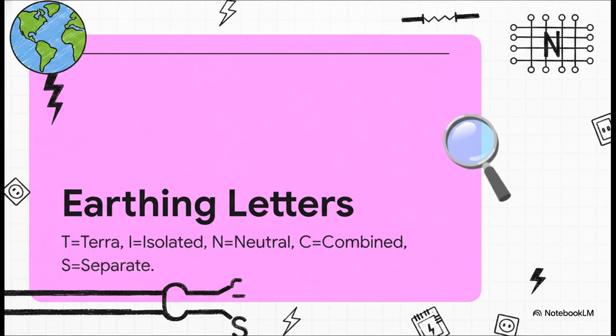Before we dive into the schematics, we need to decode the alphabet soup that BS 7671 uses to categorize these systems. The first letter always tells us about the power source, and the second letter tells us about your specific building's setup. So T comes from terra in French, meaning a direct connection to the actual ground. I stands for isolated, N means neutral, as in connected to the supply network's ground, and C and S just stand for combined or separate protective and neutral wires. Keep this vocabulary tucked in your brain for a second.